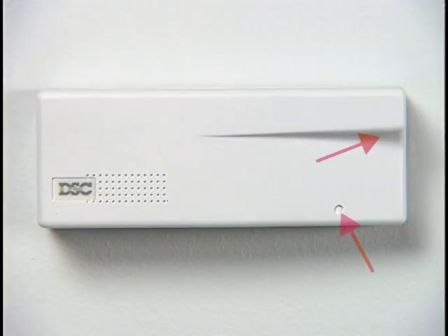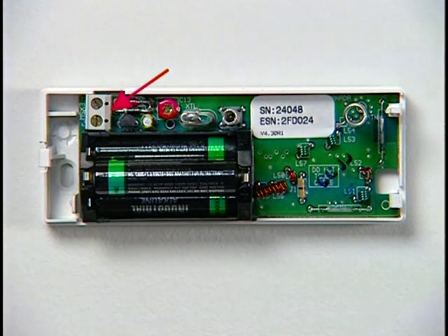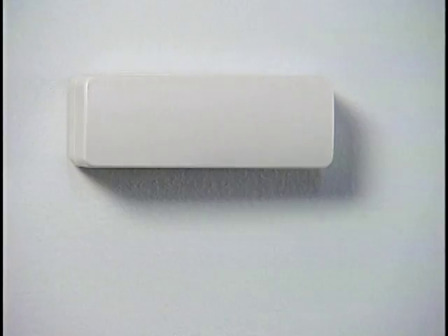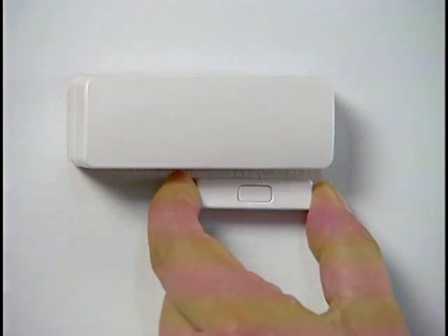To test the WLS907 door-window transmitter, either use a magnet to violate and restore one of the built-in reed switches, or open and close the zone wired to the normally closed inputs on the unit. Make sure to wait 5 seconds between activations. To test the WLS915 door-window transmitter, use a magnet to violate and restore the zone.